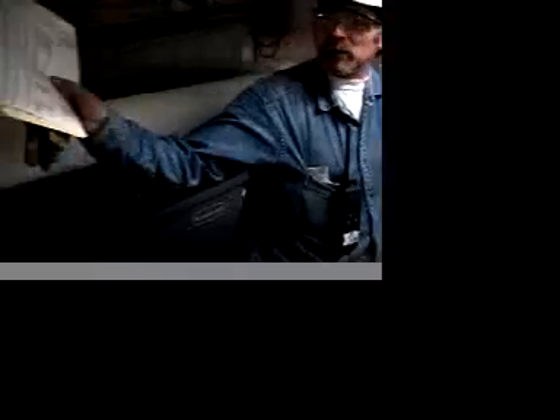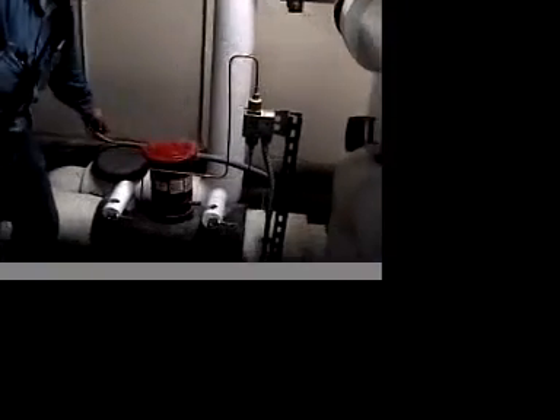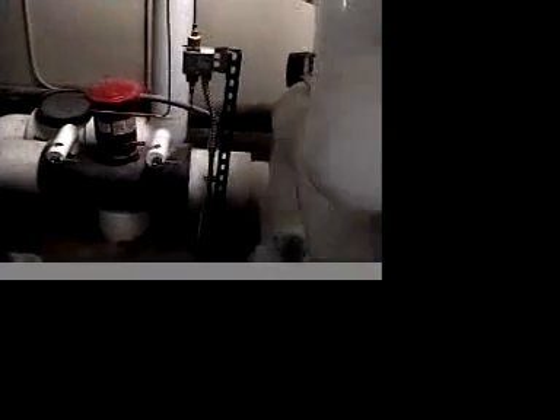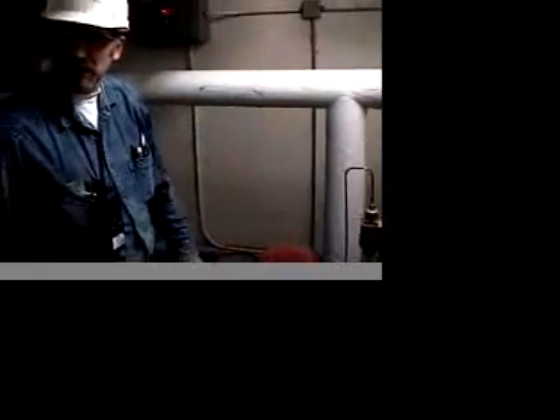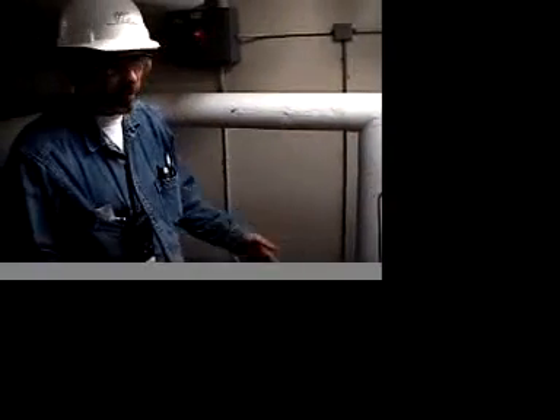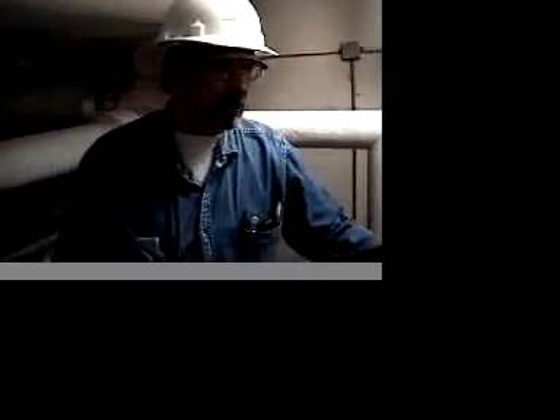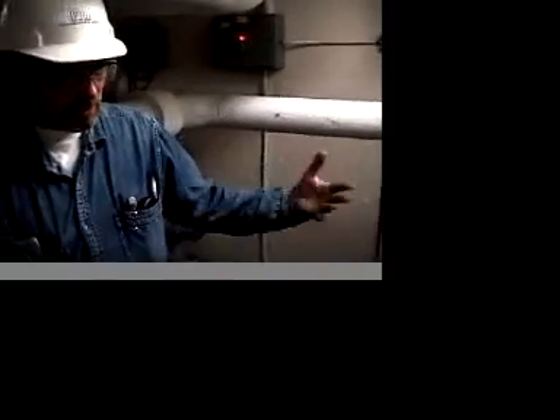If the control valve is satisfied and you don't want any more water, it shuts, and then the water comes back this way through a check valve and back through the pump and just recirculates for freeze protection. So that's pretty much all that's here. You've got valves for shutting off each one of the coils if you have a problem with a coil. But the pump should always be running.